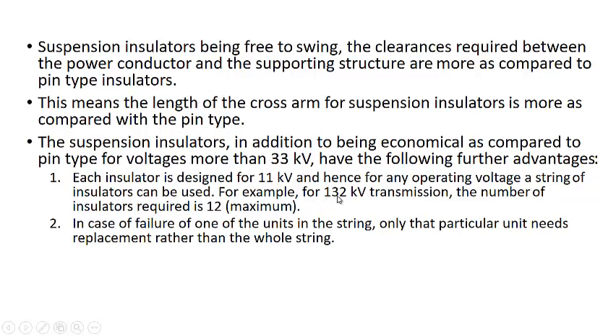that is 132. But in practice this 132 kV is the line-to-line voltage, and the voltage that appears across the insulator string is the phase voltage. So for a 132 kV system, the phase voltage will be 76 kV, because I have simply divided by root 3, it comes out to be 76, or I can take it as 77 kV. Divided by 11, we get 7. So in actual practice 7 disc insulators are sufficient to bear the voltage of a 132 kV transmission system, because please keep in mind, it is the phase voltage that appears across the insulator string rather than the line voltage.